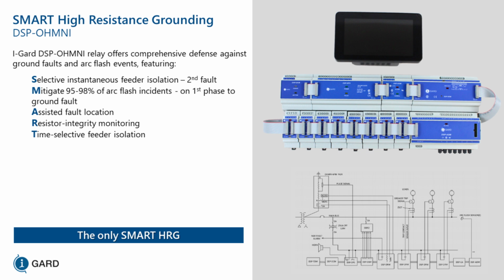So we had one particular customer who said, I don't want my electricians to become complacent, so I'm going to give them 8 hours to find the ground fault. If they don't find it in 8 hours, I'm going to trip right away. So you have time selective feeder isolation. You have 8 hours to find the fault. If you don't find the fault in 8 hours, if it still persists, we're going to trip that feeder.